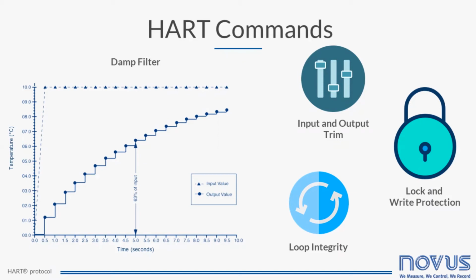Input and output trim is a command that can be sent to the device to perform adjustments or calibrations in input and output separately. The adjustments are of gain and offset on the initial and endpoint. A commissioning helper is the loop integrity feature. The loop could be checked by setting the field device analog output to a preset value, in the NOVUS transmitter's case, 4 milliamps. The analog loop diagnosis is so much easier this way.